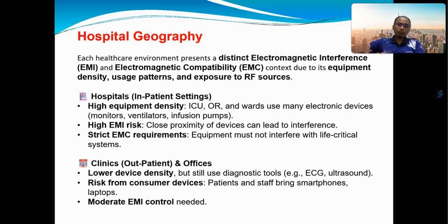Because of the high number of equipment in ICU rooms, which are located close to each other, there is a possibility that electromagnetic interference will occur in that area.